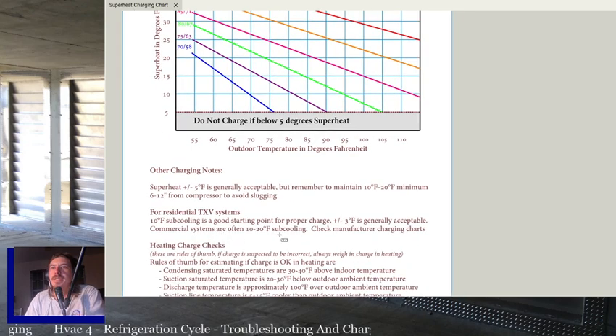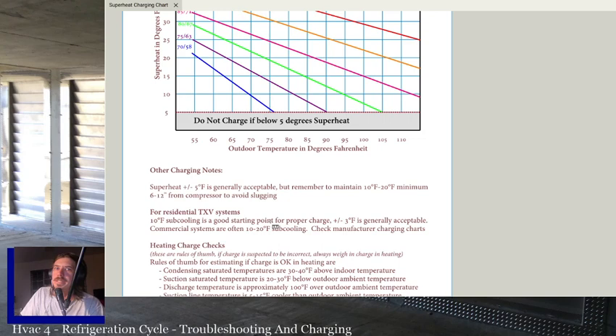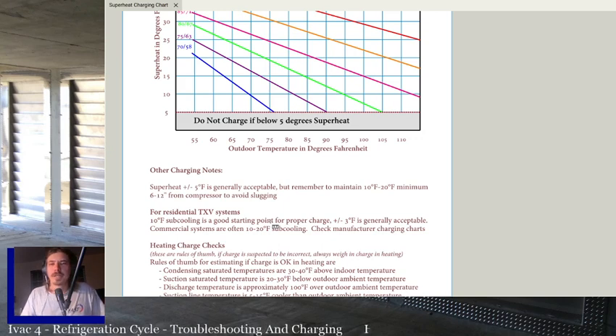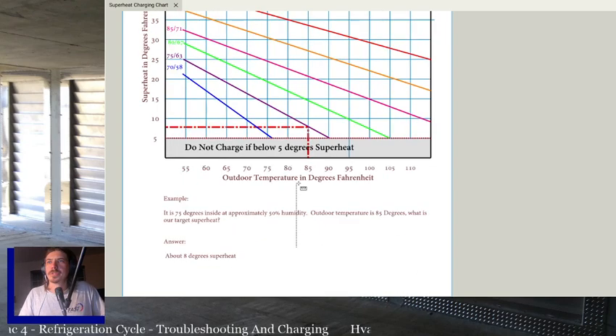The other thing I was going to say, and obviously we're going to be talking about troubleshooting these things, so you're going to need all these readings anyway. But if you're charging a TXV system, do not only check subcooling, please check superheat. Always check superheat, because superheat is more important than basically every other number. Superheat is what dictates whether or not that compressor is going to stay alive. So if you're not checking superheat, you're doing it wrong. I don't care what other measurements you need to check, check superheat. Might as well do it while you're there. Catch a problem if it's there. Catch the bad TXV while you're there. Whatever you've got to do, always check superheat.